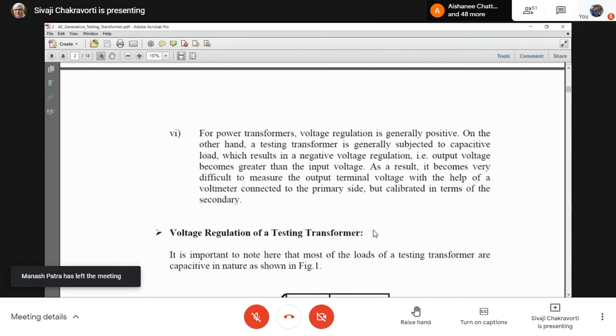Is it possible that voltage can go up? In case of capacitive load, sir, it may. Correct. Not only capacitive load, current flowing through inductive impedance, then this voltage can go up. So voltage regulation by definition, please don't say voltage drop. It is the change in terminal voltage from no load to full load. It could be drop, it could be rise. And the whole thing depends on the type of current that is flowing.